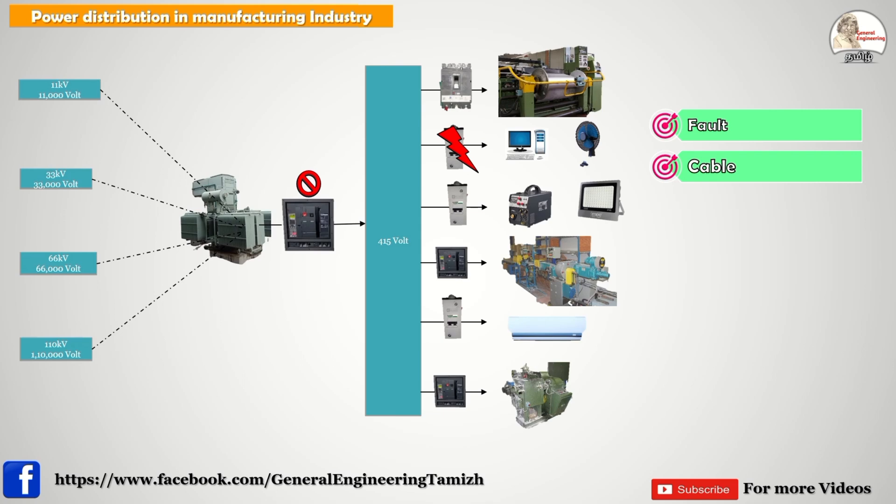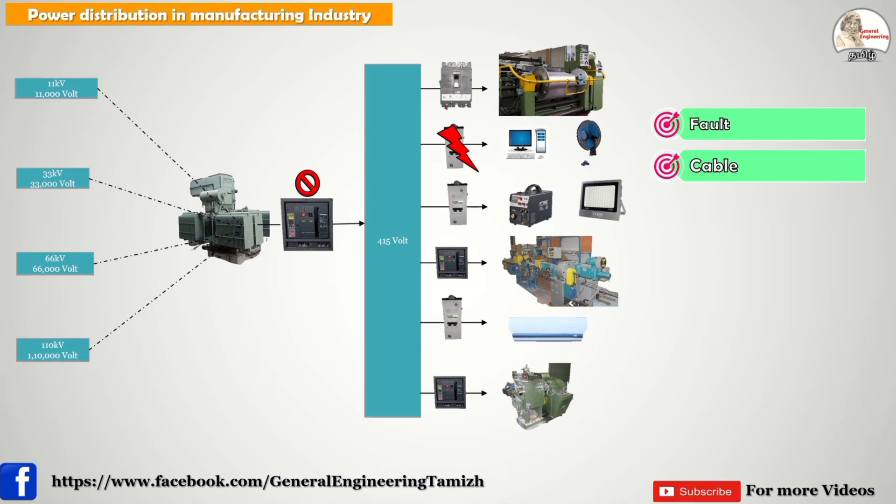The next scenario is cable size. Different rating equipments are connected in one panel, and based on the rating we have to choose the cable size, and based on the cable size we choose the proper bolts and lugs. If we use different sizes of bolts and lugs in one panel, it can create spark issues or heating issues and may lead to a serious fire incident. So this system is not good for us.